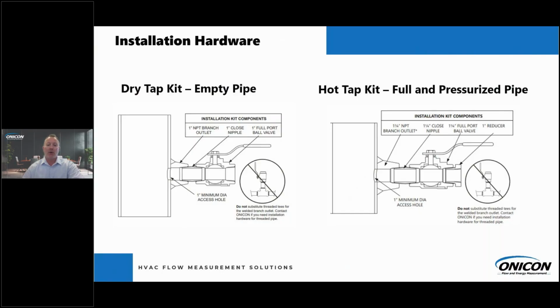As well as on the right, we have the hot tap kit. So this is great for a live pressurized system. It's actually a 1.25 inch ball valve, and that's for that hot tap drill to thread in, and you're able to drill into a live pressurized pipe.